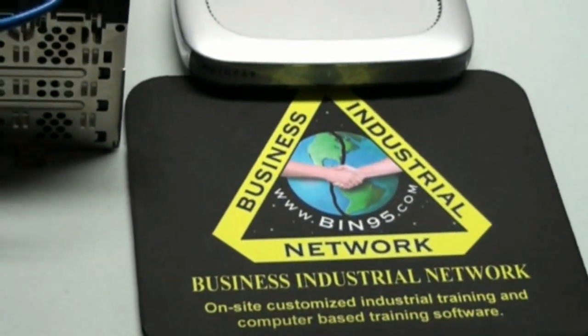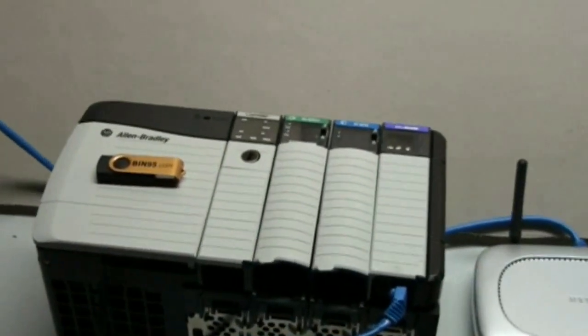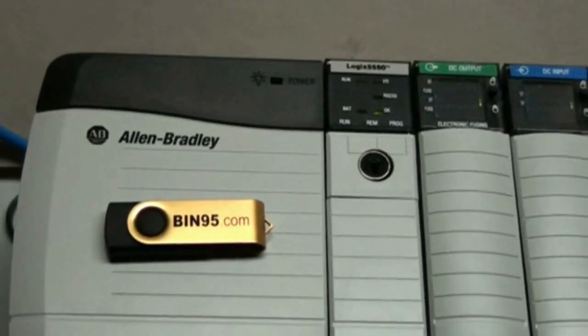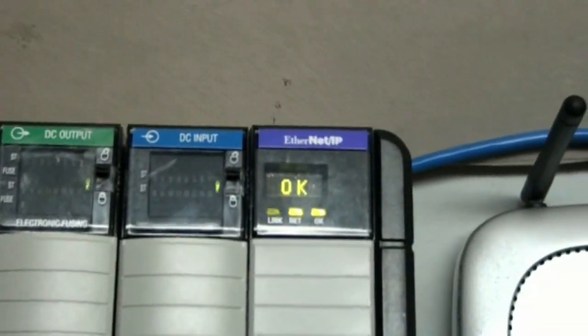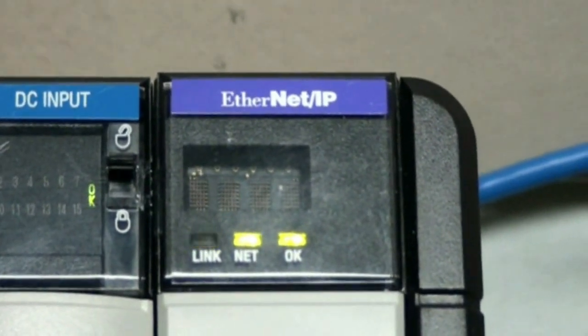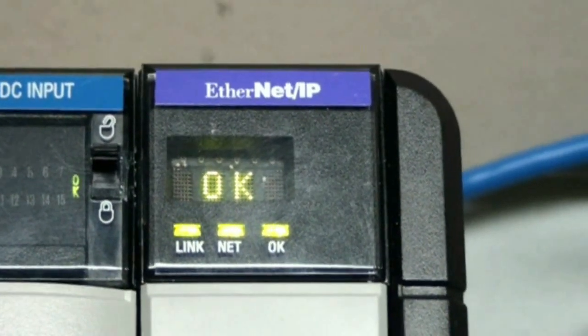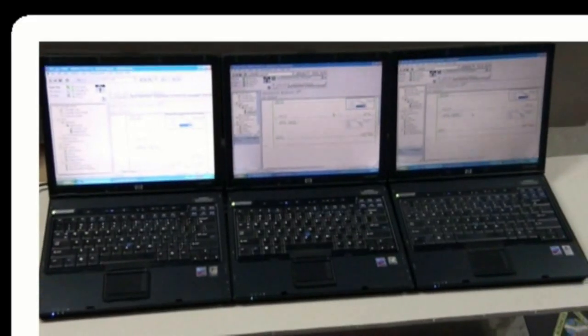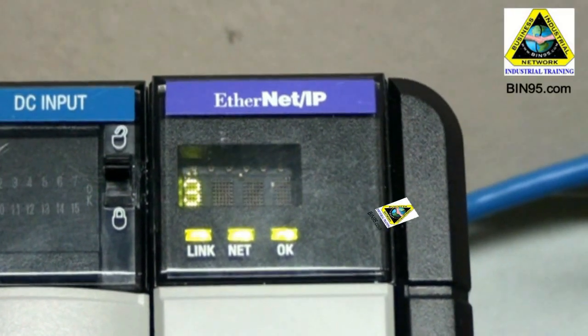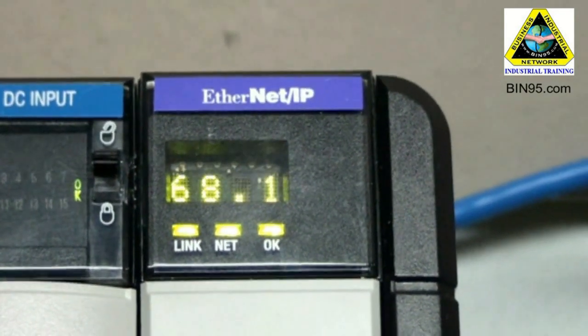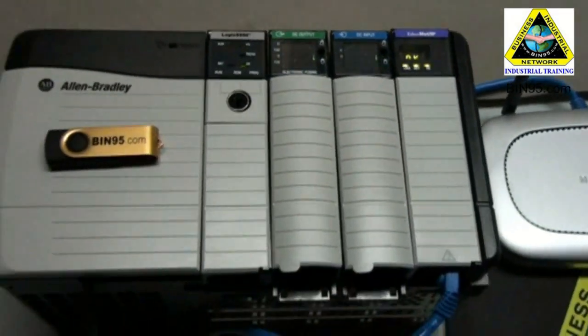Brought to you by Business Industrial Network. As you can see on the ControlLogix PAC — Process Automation Controller, some people refer to it as a PLC, same difference, almost — here is what your Ethernet card should look like. When everything's working properly, you should see an OK, the IP address, and since we do have computers, you'll see the net light is on solid. Typically you'll have the link connection as long as there's something linked to it, and you'll have the OK on there as long as everything's OK.